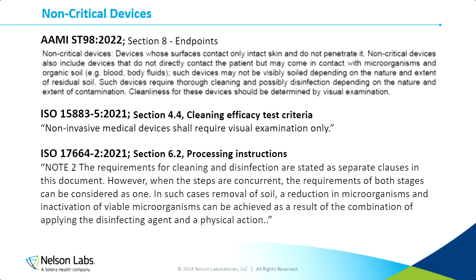And branching more on those non-critical devices, Griffin had talked about this. A non-critical device is a device whose surface either contacts intact skin or does not directly contact the patient, but it could still see some organic soil or microorganisms like blood or bodily fluids. In ST98, it states right here, cleanliness for these devices should be determined by visual examination. ISO 15883-5 also references this: a non-invasive medical device shall require visual examination only.